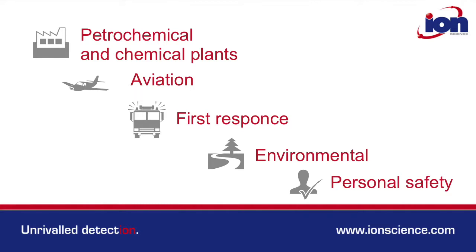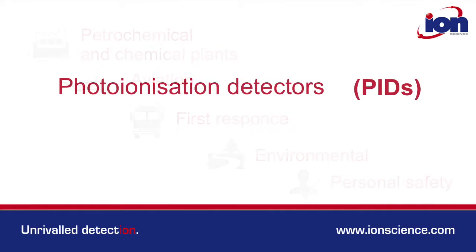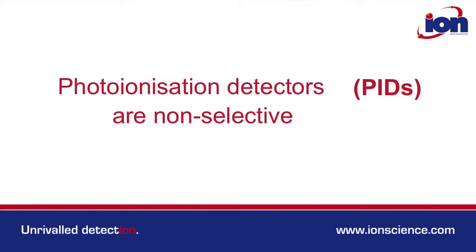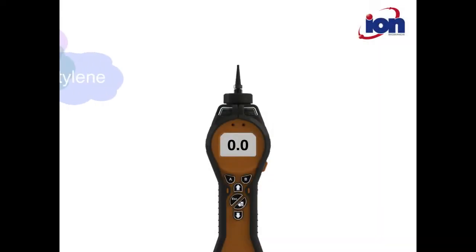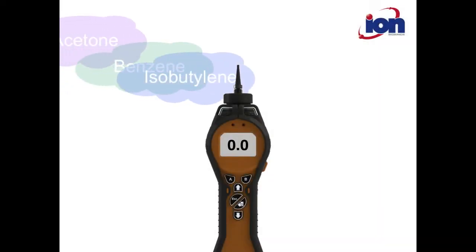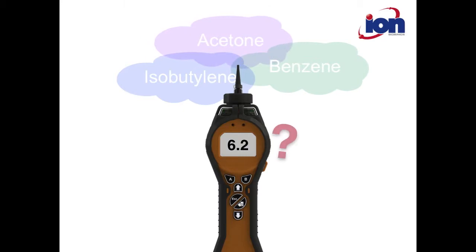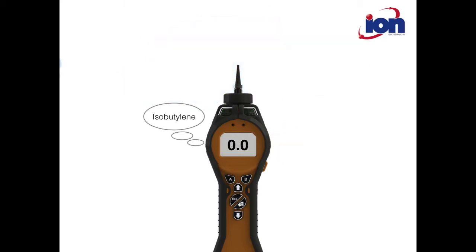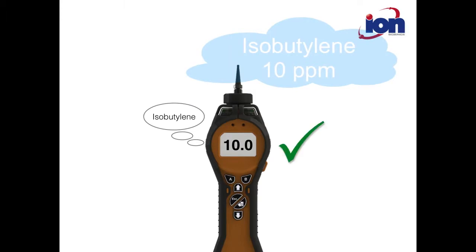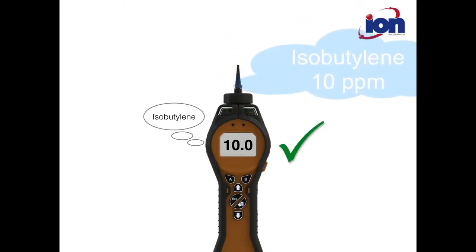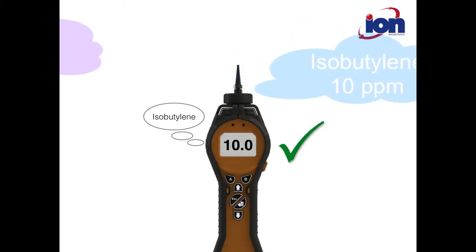For all these great features, PID is non-selective — it can't differentiate between the gases it detects. The detectability of PID towards gases also varies; for example, a concentration of one gas may give a different response to the same concentration of another.